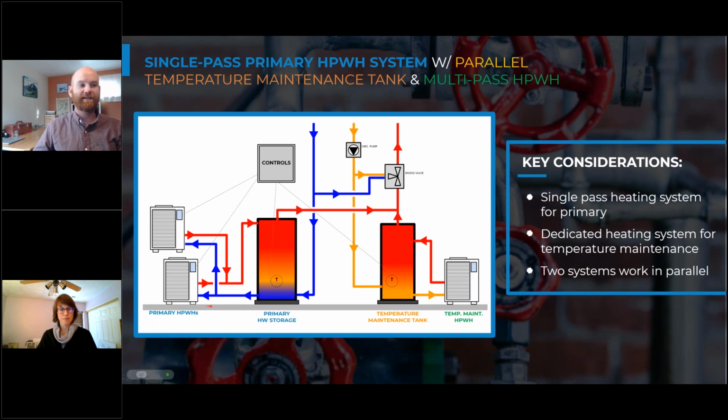Most technologies can deal with it fine, but some of the early generations of heat pumps would result in system errors or a system restart required because of that shock in change of temperature of the entering water temperature on that cold side.